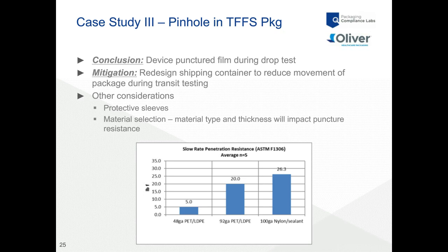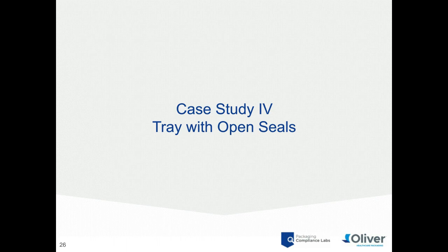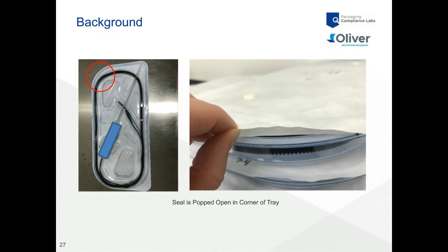In this bar chart, we're looking at a slow rate penetration test, ASTM F1306, and the pound force required to puncture some of these films. You'll see from left to right, 48-gauge polyester, really the workhorse of our industry with respect to pouching materials, then 92-gauge, a little bit beefier structure, and on the far right, 100-gauge nylon structure. You can see there's quite a bit of difference in puncture resistance when you compare a beefy nylon structure to a 48-gauge polyester. So if you have sharp components as part of your medical device, you really want to consider going to some of those different materials and beefier structures.